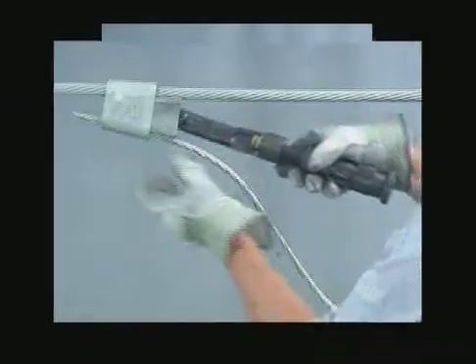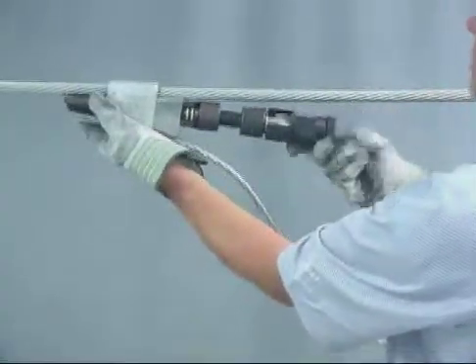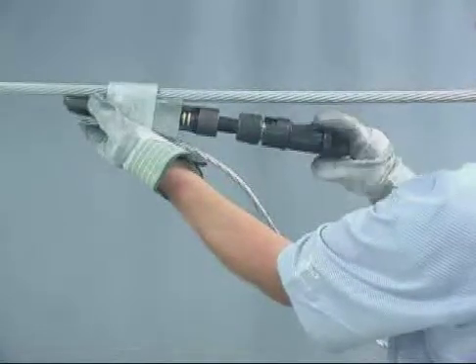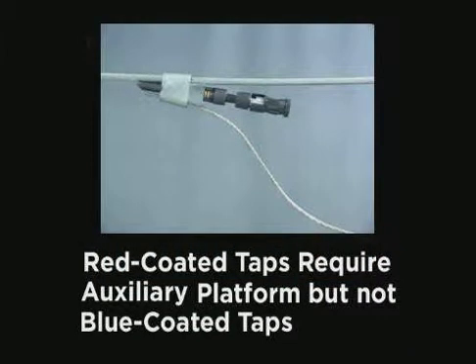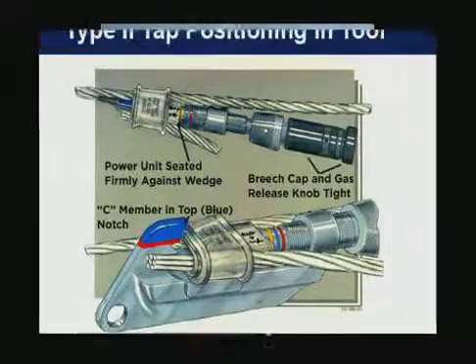To position the tap in the tool, the C member must be located in the correct positioning notch with the open side facing the tool head. Turn the coupling nut until the power unit is seated firmly against the wedge. When applying red-coated taps, the auxiliary platform must be used. Blue-coated taps do not require a platform. Type 2 taps are color-coded white and do not require the auxiliary platform. The C member is positioned in the blue notch of the tool head. If the tool is correctly positioned on the tap, it should be self-supporting.